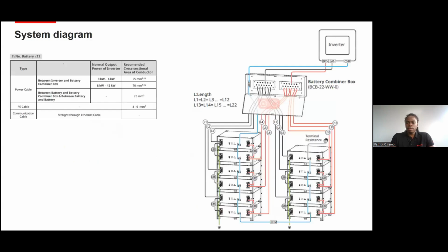If I may move forward, you can see these batteries are stacked more, about 11 to 12 pieces, a minimum of 12 pieces. The battery module can be stacked in under 12 pieces. GoodWe does offer a combiner box, which is recommended to be used. Importantly, do note the technique that we are displaying in this wiring. The batteries are grouped in twos, primary twos. This allows balanced charging and discharging, and in this sense you'll be fully utilizing the long life cycle of the battery.